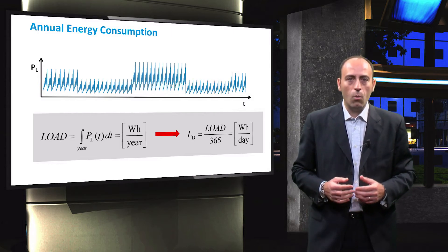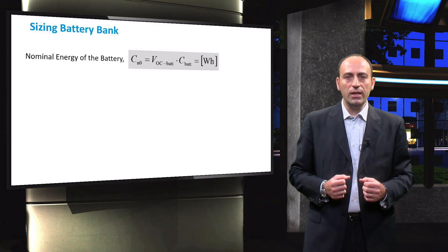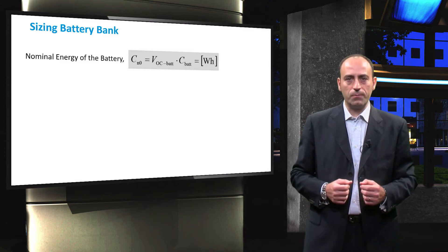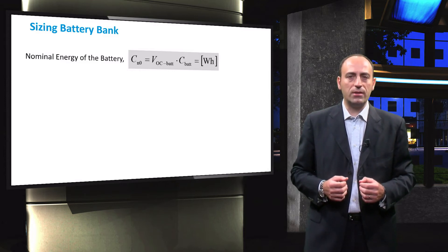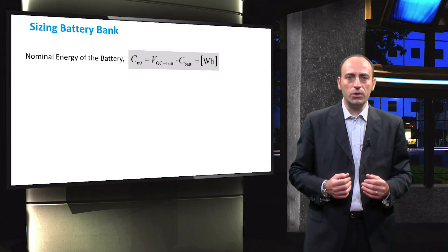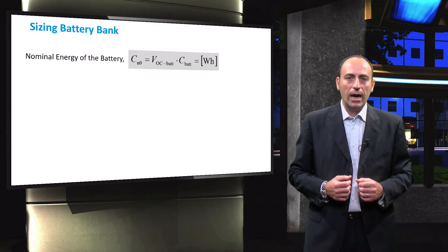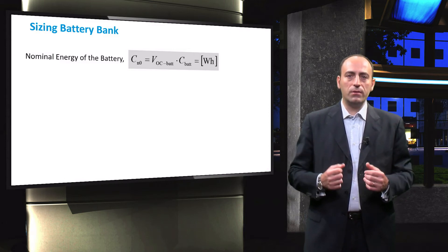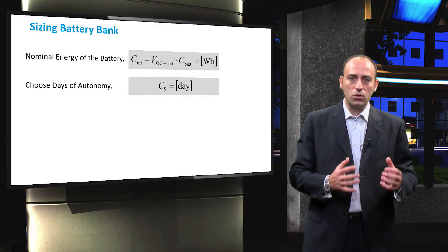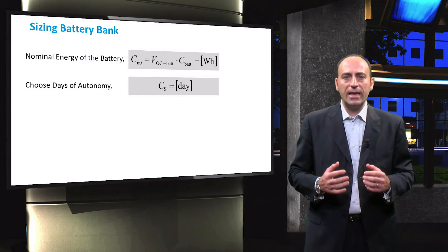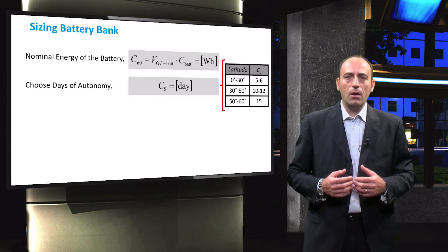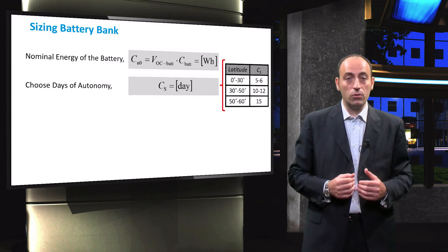The average daily demand is obtained by dividing the annual energy demand of the loads by 365 days and is expressed in watt-hours per day. Once the daily load demand is calculated, a particular battery is chosen for the PV system from the market. Its rated energy capacity, CN0, is noted by multiplying its open circuit voltage and its rated capacity. After this, an adequate number of autonomous days, CS, is chosen. As you saw in the video about loss of load probability, this selection can be made using the following table as a guideline. For example, places close to the equator can have fewer autonomous days.